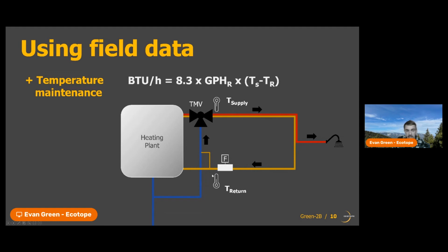So if we measure the return temperature at the same time, we're going to see a really big temperature differential, which is going to result in a really high BTU per hour reading. And the other way around, if this mixing valve temperature drops really quickly, then we're still reading this high return temperature because it takes a while for this water to get all the way around the loop. So maybe your mixing valve drops from 125 to 120, and now your return temperature at that same moment is still 122. Now our temperature differential is negative.